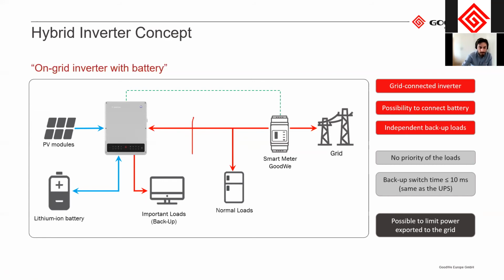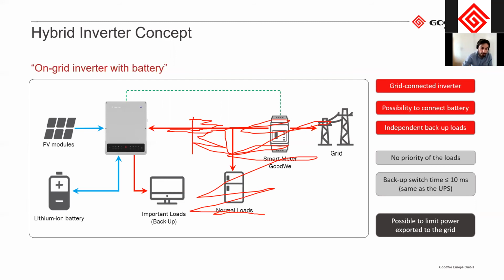So this disconnects, and this means that all those loads will be disconnected, but internally it will switch over to only supply the backup loads from the battery and the PV modules. And the reason why this one needs to disconnect from this one is in the grid codes of almost all countries, I would assume, because if the grid fails and someone needs to work on the grid to fix it, then they don't want your inverter to send out power to the workers working on the grid.